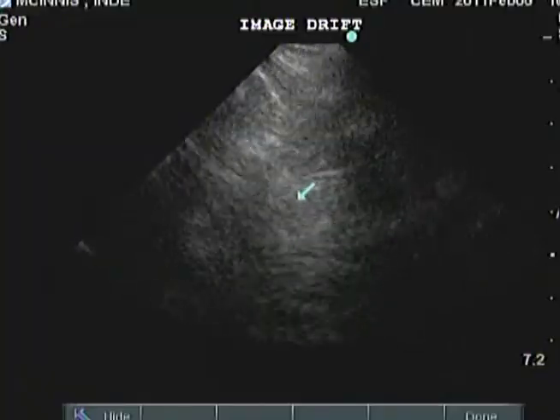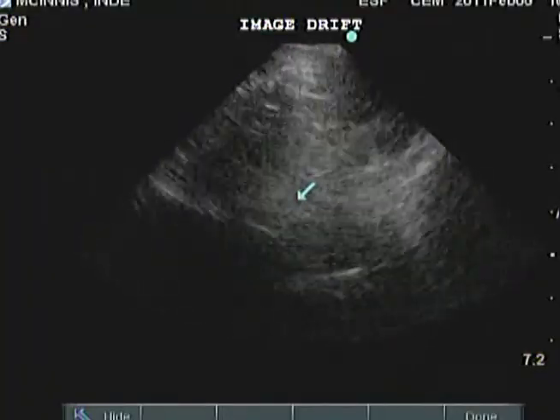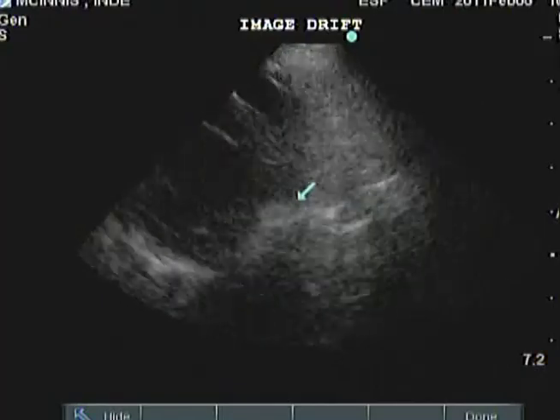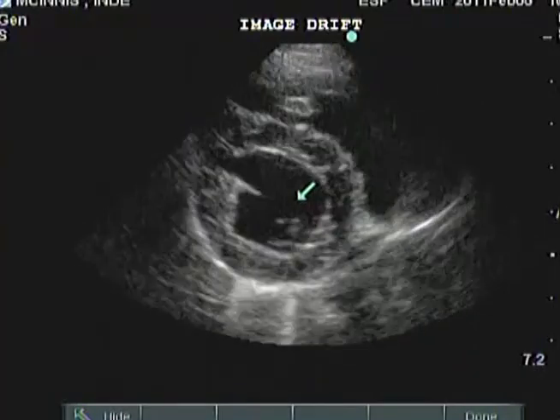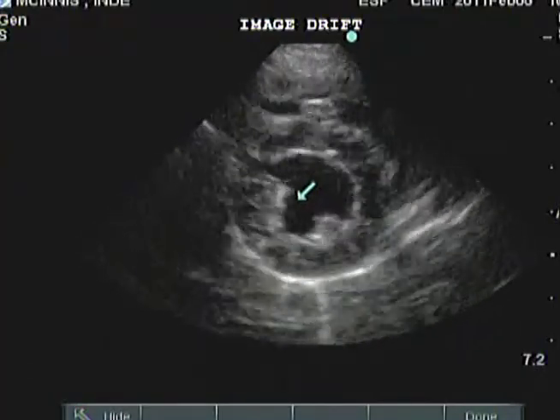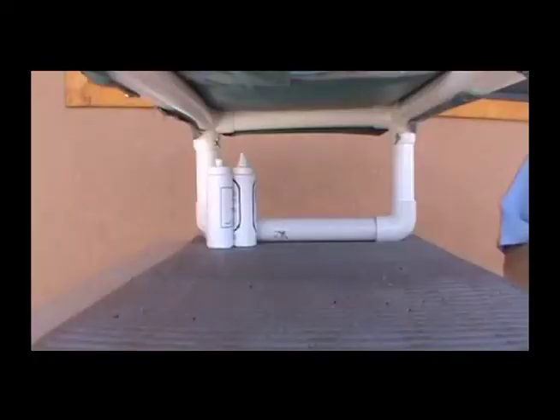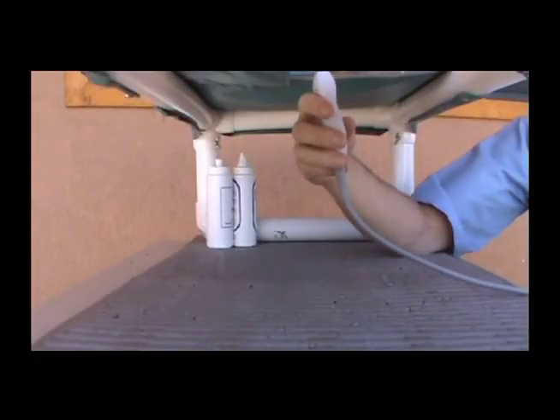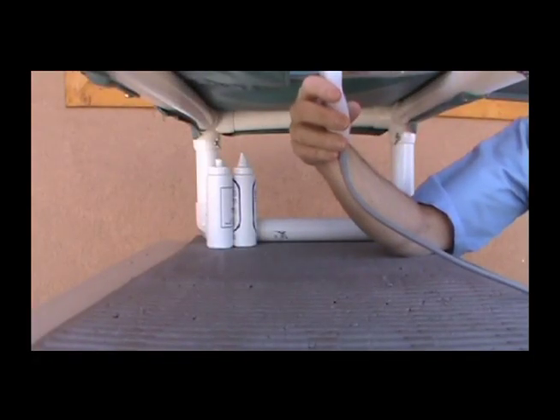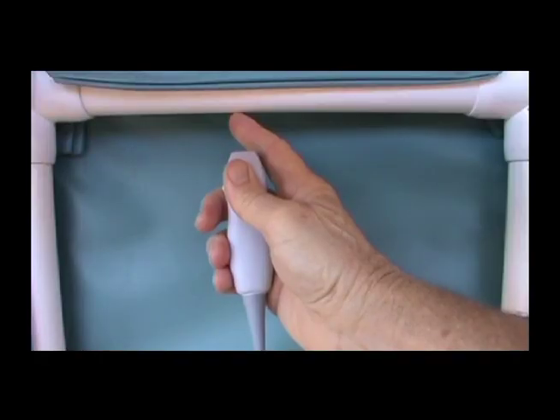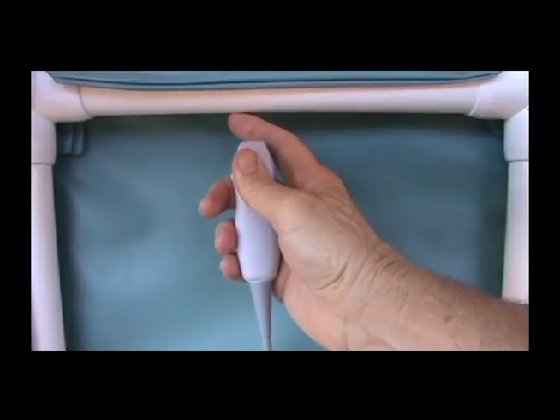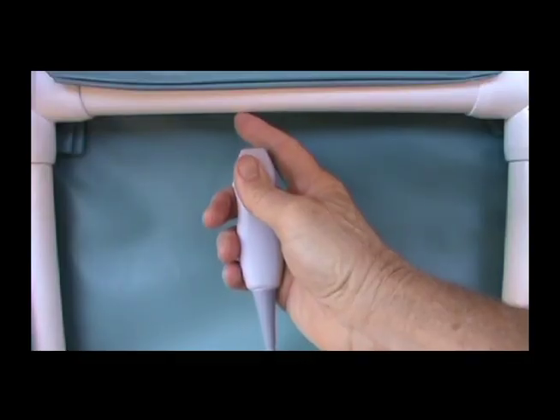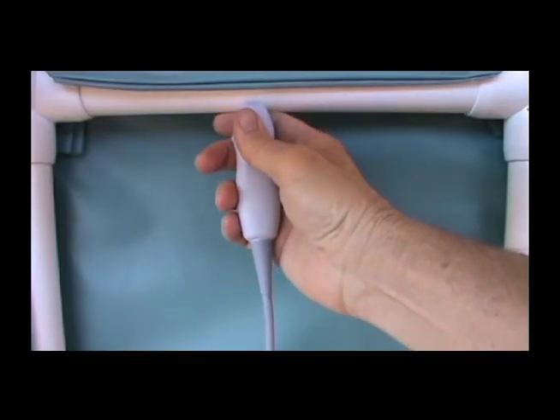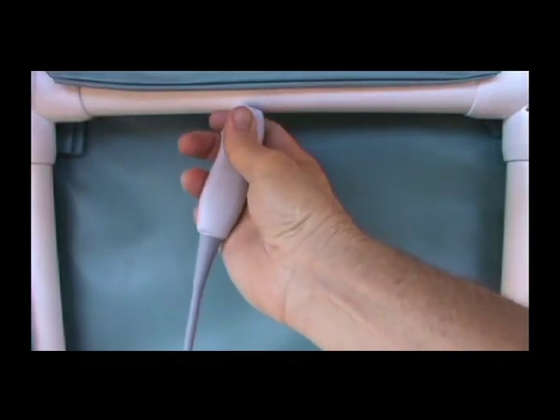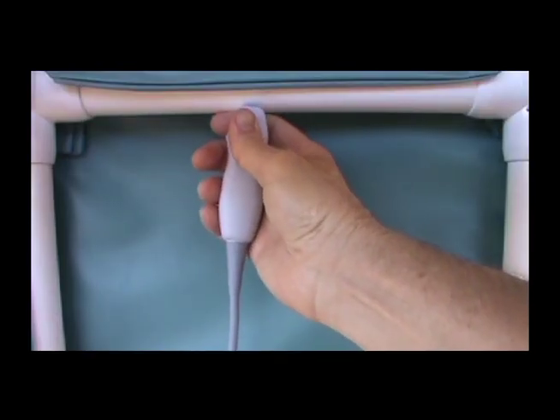If the cardiac image is drifting, it is because you are unintentionally moving the transducer. The best way to prevent image drift is to anchor the elbow of the transducer arm to the rubber mat and anchor the index finger of the transducer hand to the patient. Then anchor the transducer to the index finger.